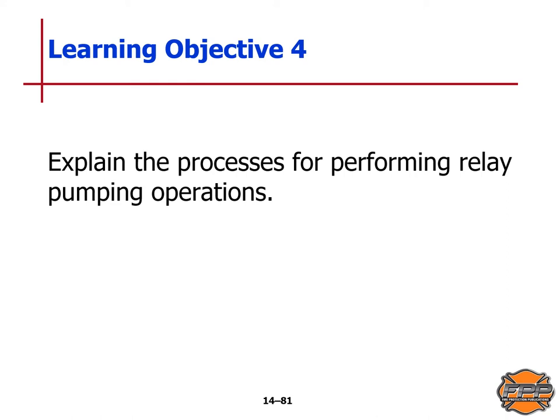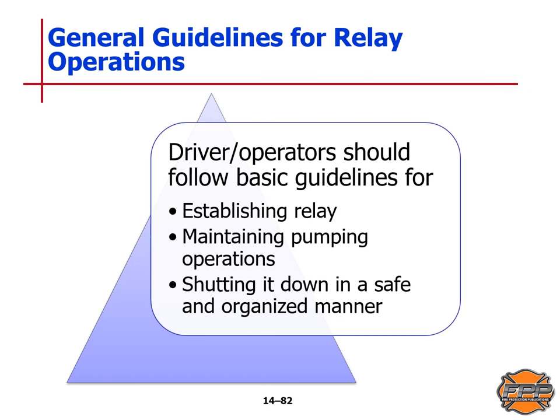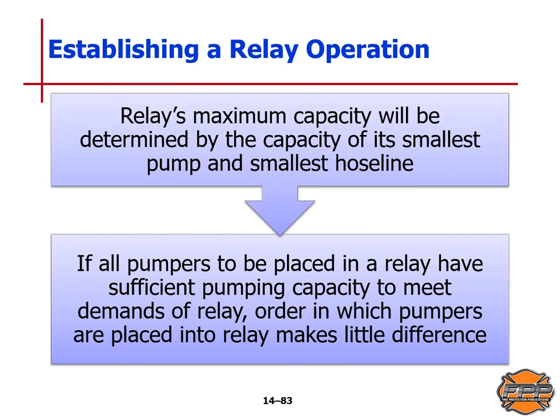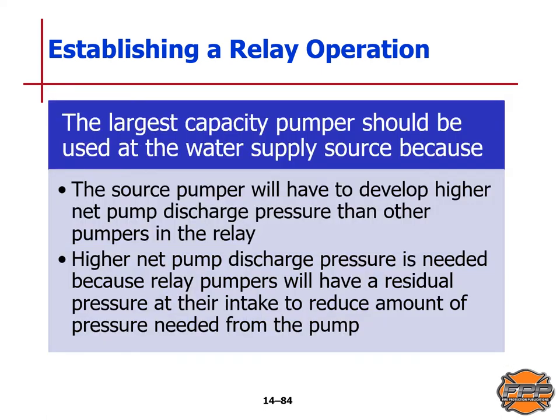Learning Objective 4: we will explain the processes for performing relay pumping operations. General guidelines for relay operations — driver operators should follow basic guidelines for establishing a relay, maintaining pumping operations, and shutting it down in a safe and organized fashion. The relay's maximum capacity will be determined by the capacity of its smallest pump and smallest hose line. If all pumpers are placed in relay and have sufficient pumping capacity to meet the demands of the relay, the order in which they are placed into relay makes little difference. The largest capacity pumpers should be used at the water supply source because the source pumper will have to develop a higher net pump discharge pressure than the others.